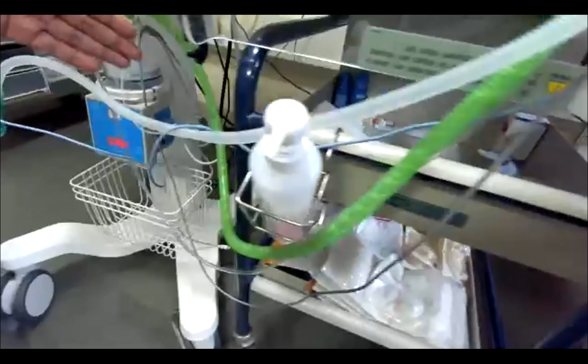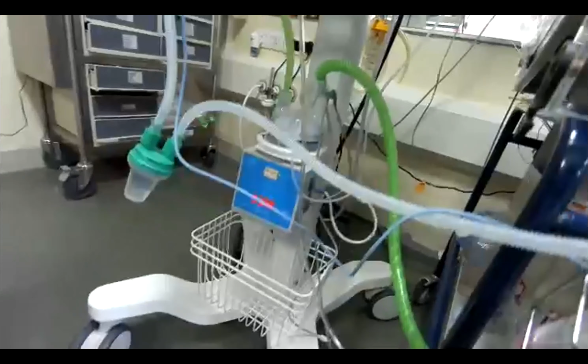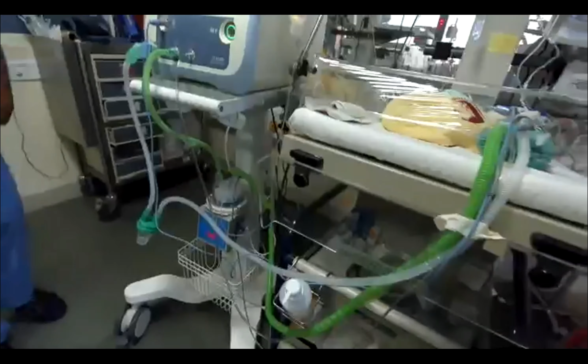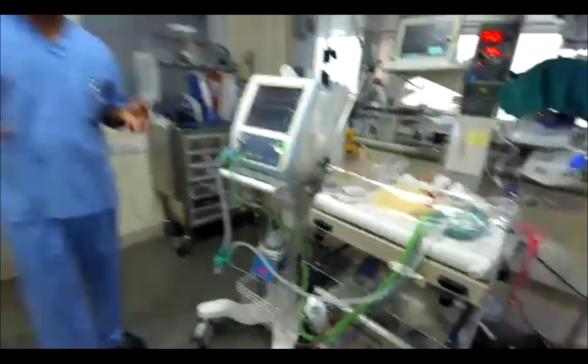So the green one is where the inspiratory circuit is. The circuit should be bone dry. There should be no condensate. I see that there is some condensate across the expiratory limb, even though I don't see any condensate in the inspiratory limb. So let us see where the fault is. One of the factors could be room temperature, sir. So do we have a room temperature? Yes, sir. The temperature is 25 currently, with 50% humidity. 25, so possibly a slightly cold room. We usually expect 26 to 28. So maybe that could be one factor.